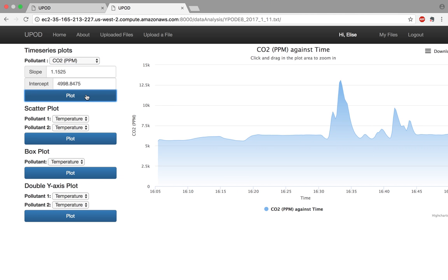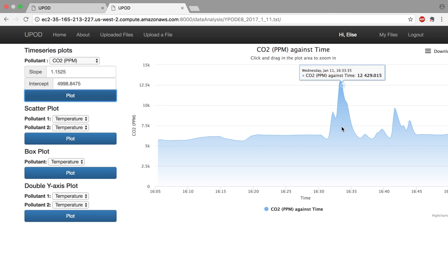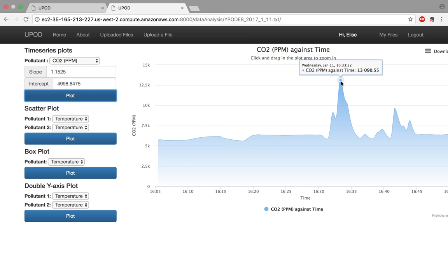As you see, same shape, but our baseline value is at around 6,000 units in parts per million. Now, when we look at our same high peak, we don't have 7,000 voltage units anymore. Now we have 13,090 parts per million. Because our y-axis says parts per million, which is in fact our concentration unit.